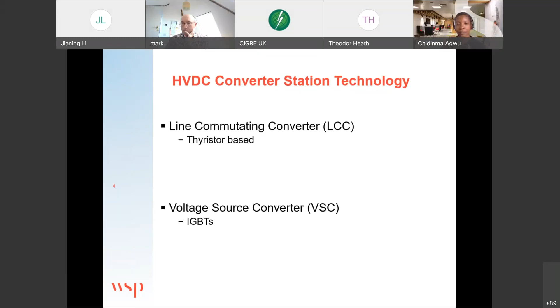This is an example of an LCC HVDC converter station, which also reminds me that I wanted to mention something that Mark had mentioned in his presentation. With your VSCs, for example, you have harmonics that are created, and it's the same with your LCC. With your thyristor technology, with your LCC converter stations, you tend to have the need for AC filters. Because you have harmonics produced on your AC side, you need to be able to take these out. You need to clean this before you transfer your power into your network. With VSCs, the harmonics that are created are a lot lower, so you don't usually need an AC harmonic filter, or they'll be a lot smaller.